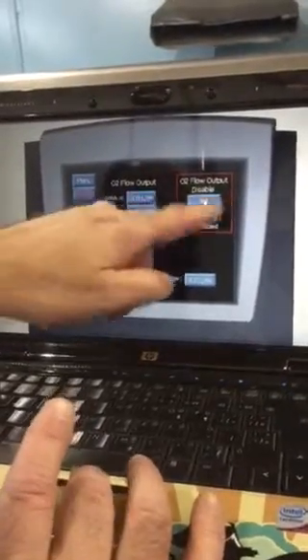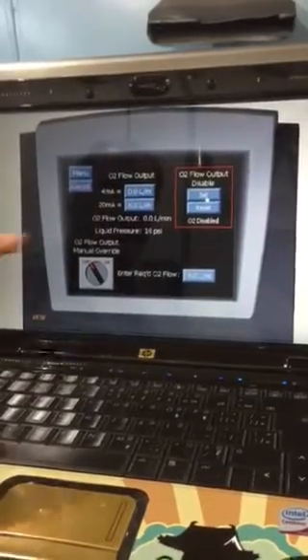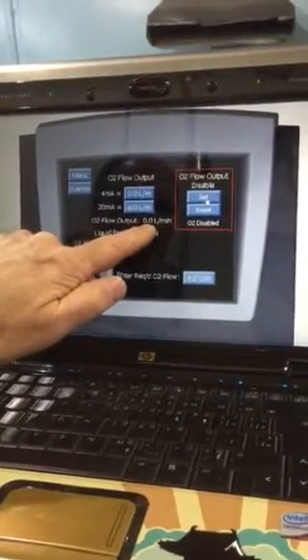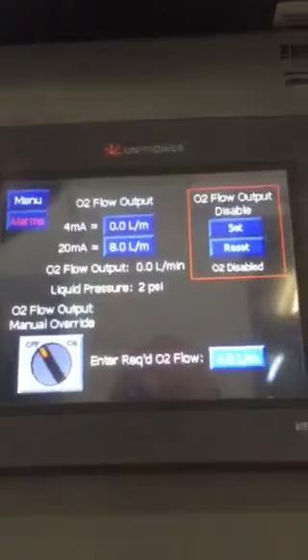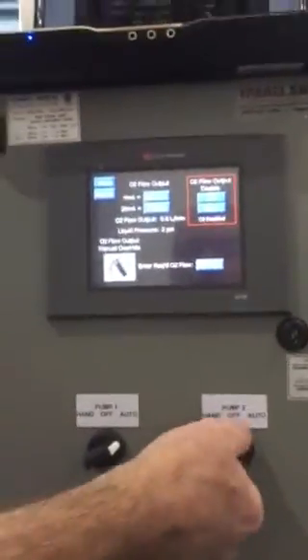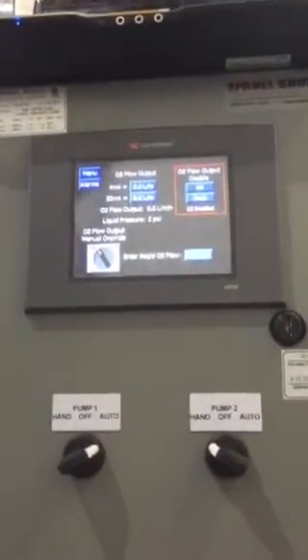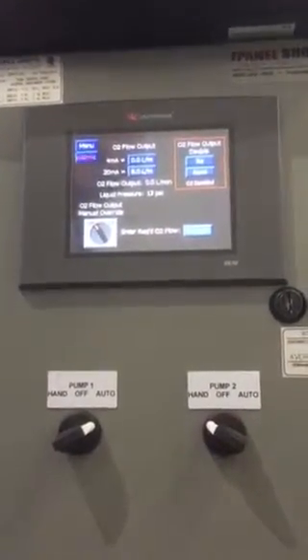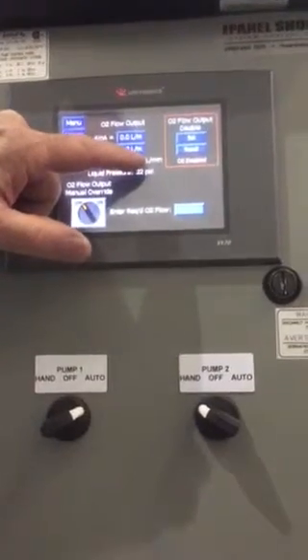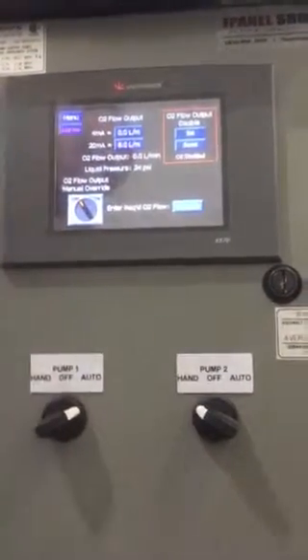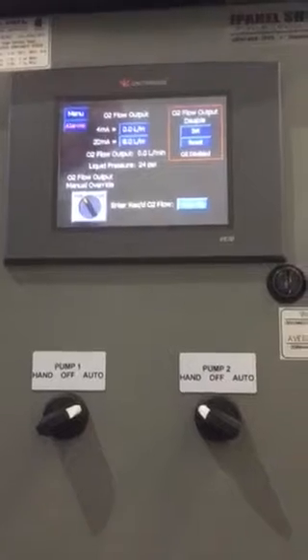So what you want to do is, if you hit flow output disable, hit the set button, it shuts down the oxygen flow. If you look down on the screen, it mirrors the same thing. You can see it set. Now if someone tries to turn the switch over to hand, the system will start, but there's only one problem with it. You are running, but you're not delivering any oxygen to the system. So this locks them out from using it if you want to do that for any reason.